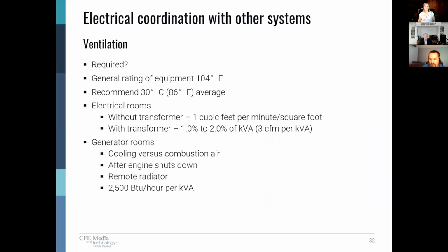Okay, I mentioned heat loads. So let's talk about the kind of things that you need to work with your mechanical HVAC engineer on. Is ventilation required? Generally speaking, the rating of equipment, particularly sophisticated switchgear with electronics and controls, you want to keep no more than, you don't want it to exceed about 104 degrees Fahrenheit. It's different for outdoor type rated equipment, but for the indoor rated gear, above that, you can start to have errors in measurement systems in sophisticated relays.